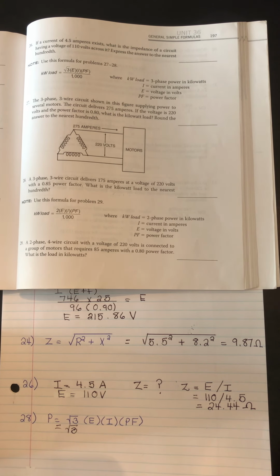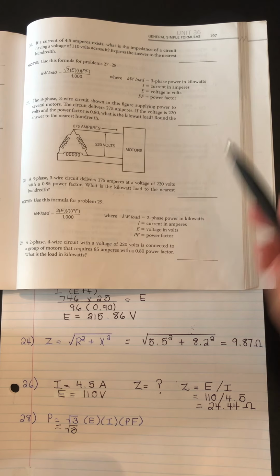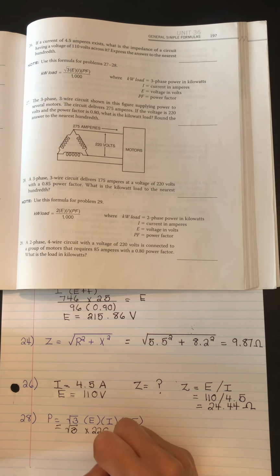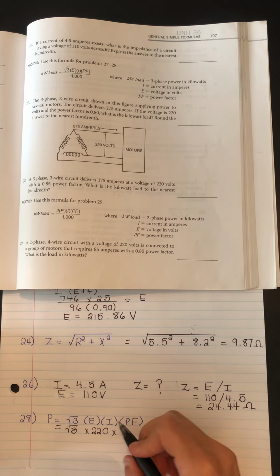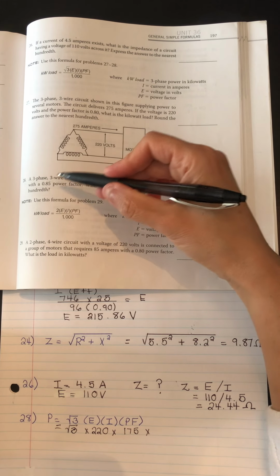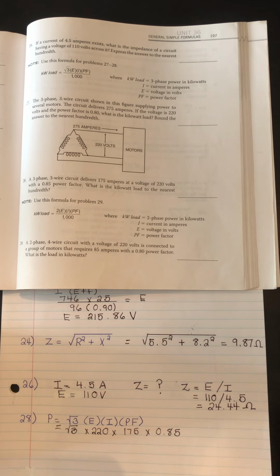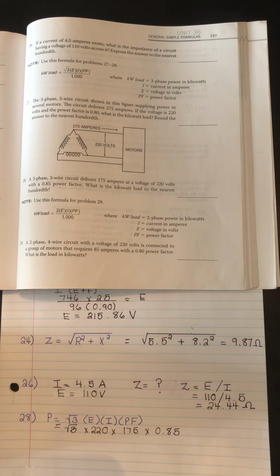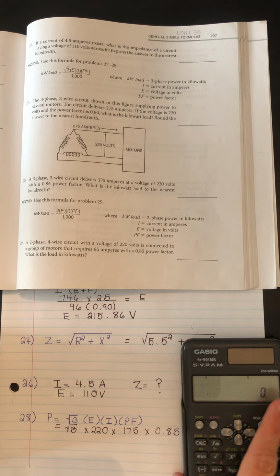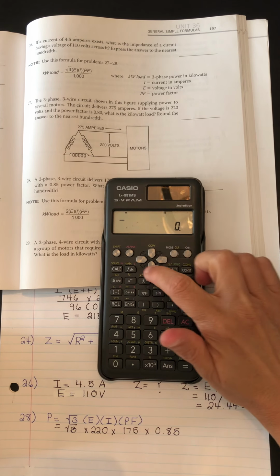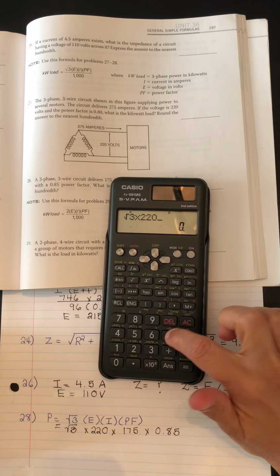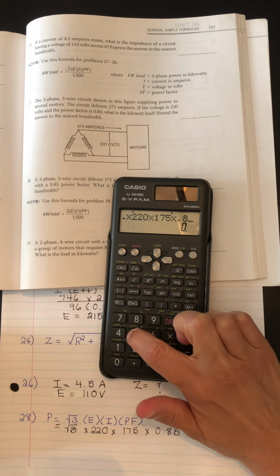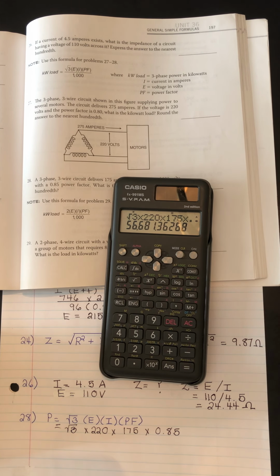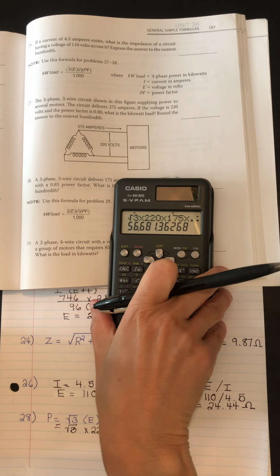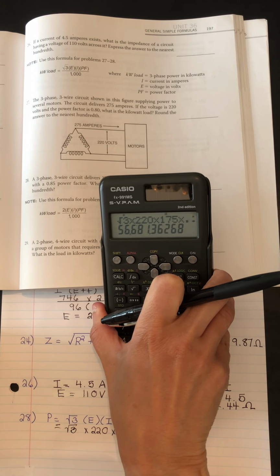So again, the voltage value is 220. The current value is 175. And the power factor is 0.85. So let's go ahead and carry that out first. So multiplication of all of those quantities. So square root 3 times 220 times 175 times 0.85. And we get this right here. So I'm going to write that down for us. And we're going to get 56,681.